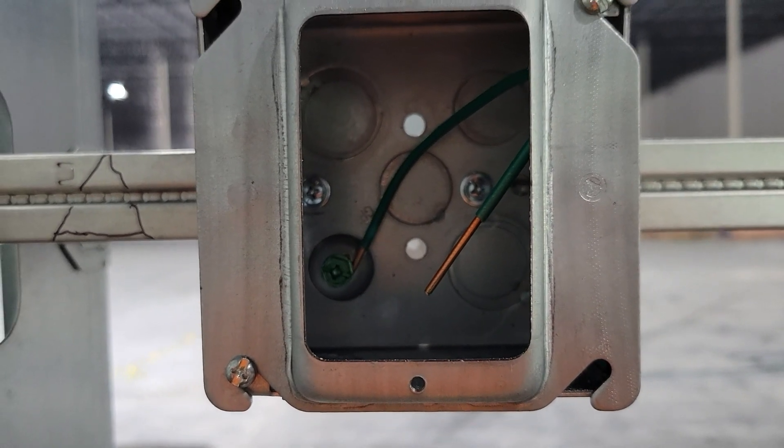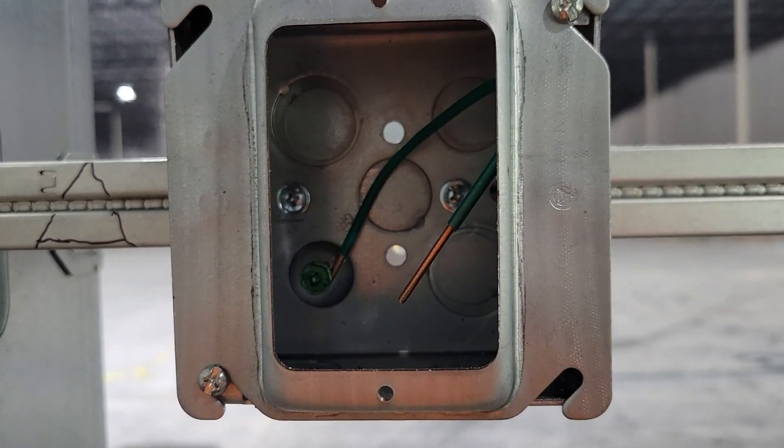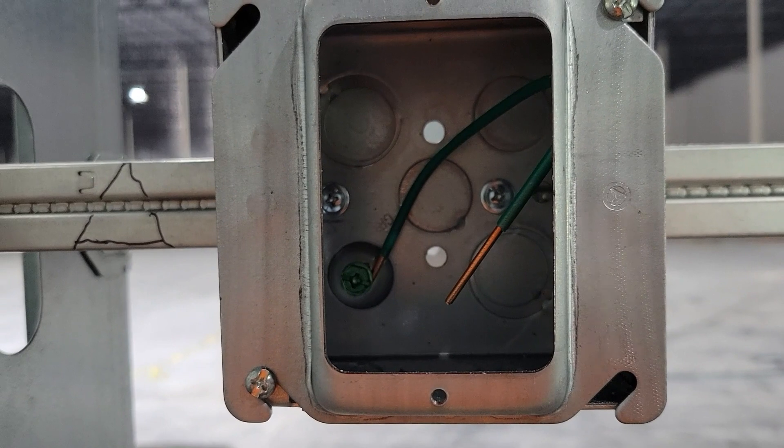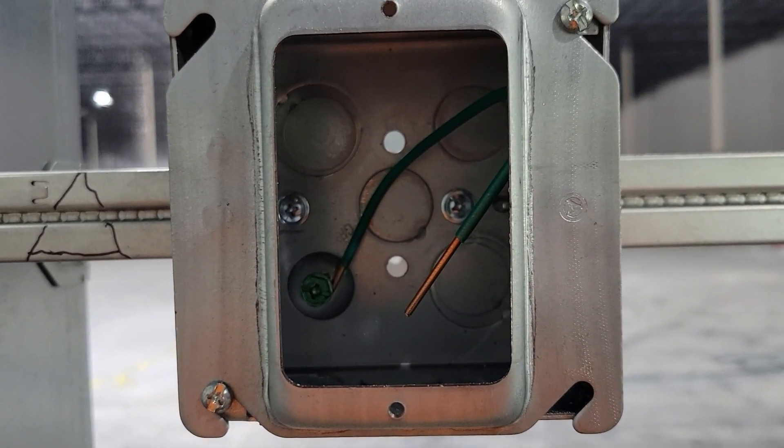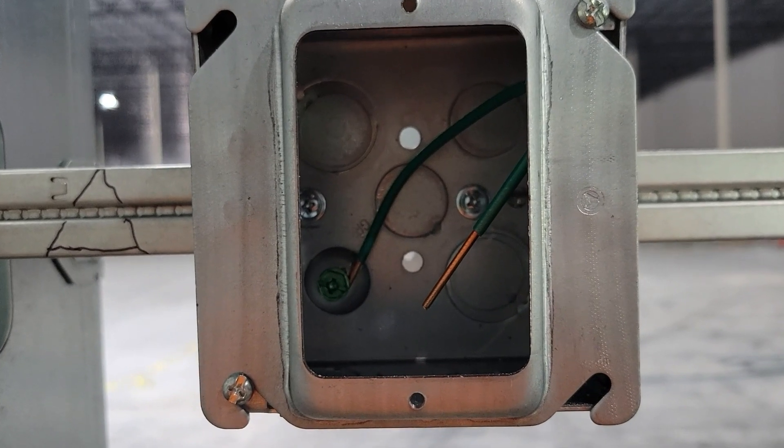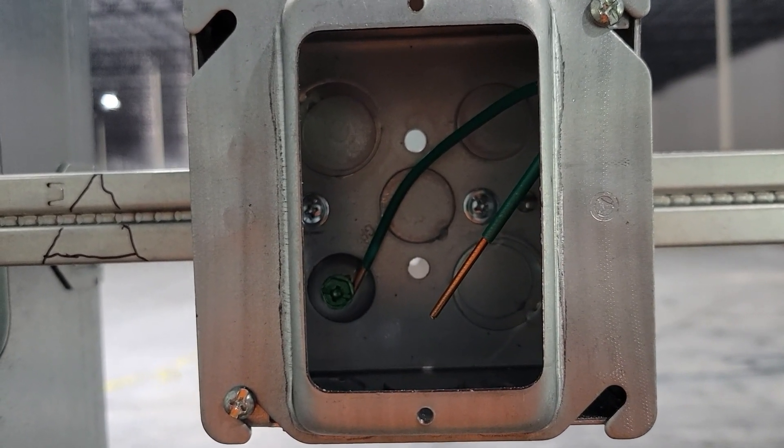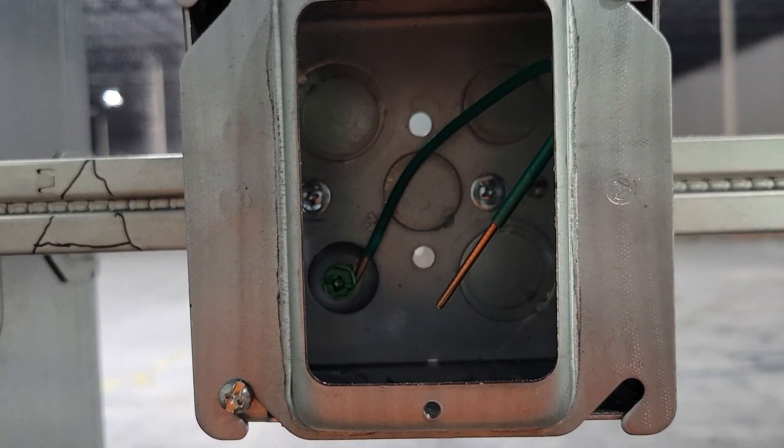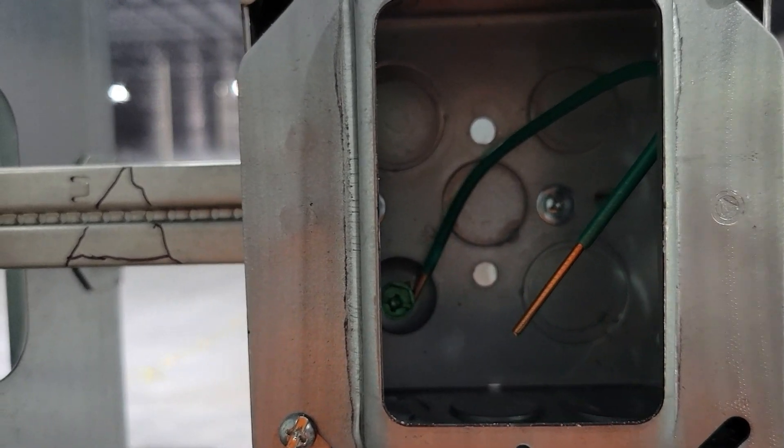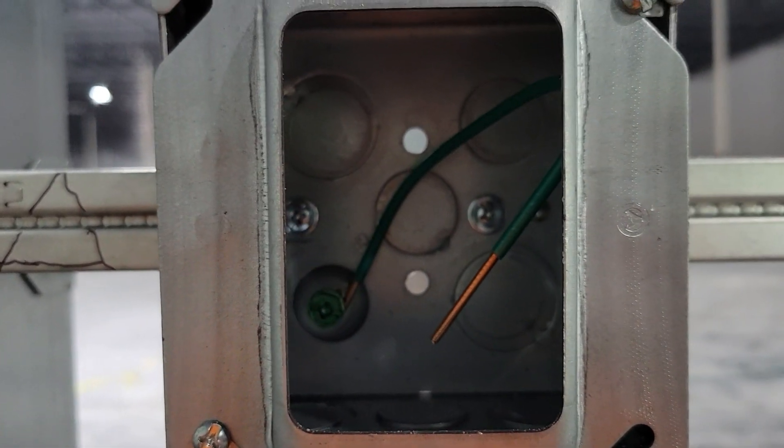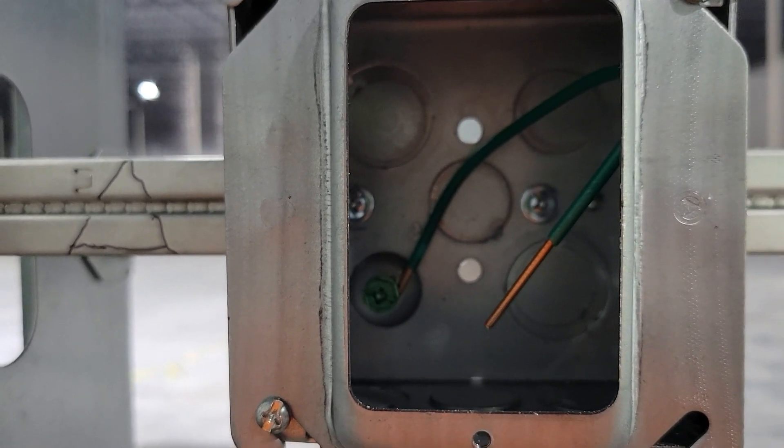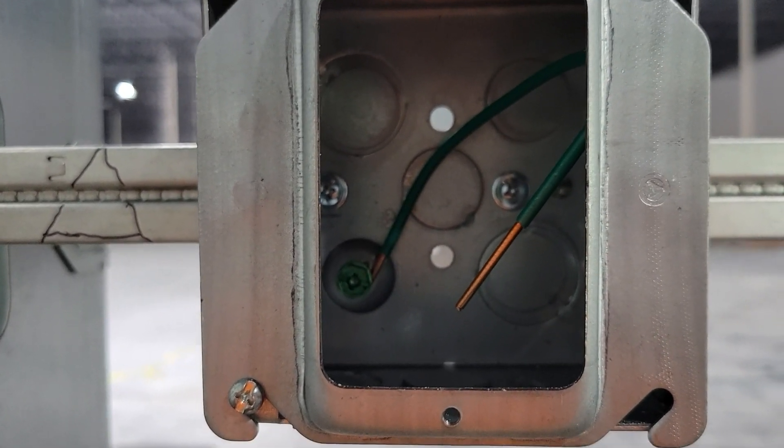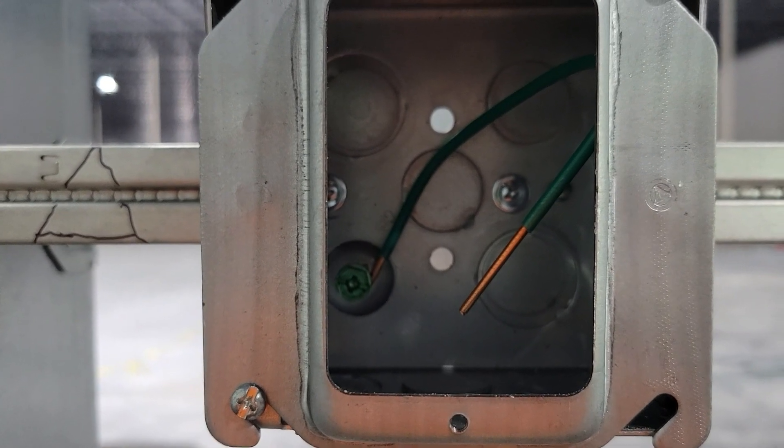It is required. Now there are certain stipulations to where you can get around that, but if you have a grounding conductor in your raceway, which means a green wire that is supplied to be the grounding conductor, then you are required to have a grounding screw installed with a copper jumper or aluminum jumper.